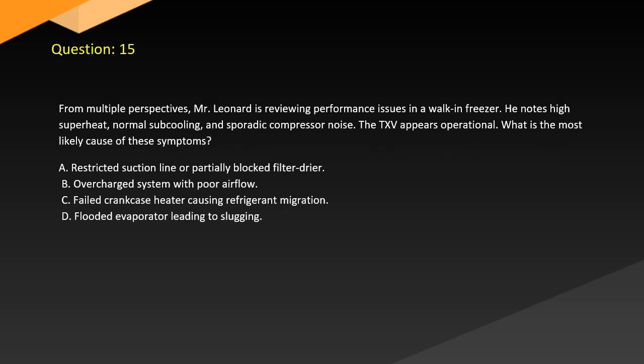Question 15. From multiple perspectives, Mr. Leonard is reviewing performance issues in a walk-in freezer. He notes high superheat, normal subcooling, and sporadic compressor noise. The TXV is operational. What is the most likely cause of these symptoms? A. Restricted suction line or partially blocked filter dryer. B. Overcharged system with poor airflow. C. Failed crankcase heater causing refrigerant migration. D. Flooded evaporator leading to slugging.